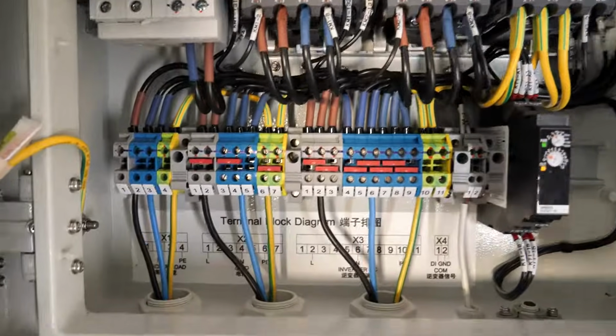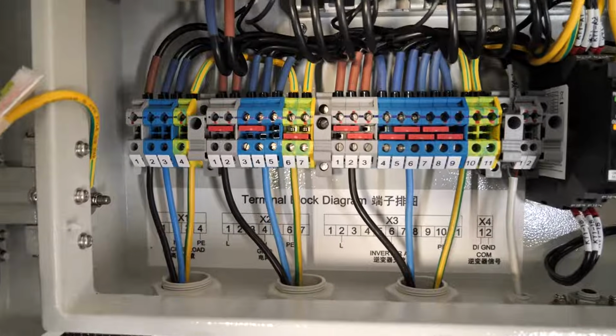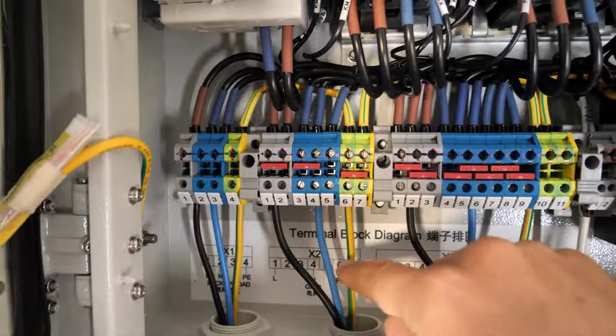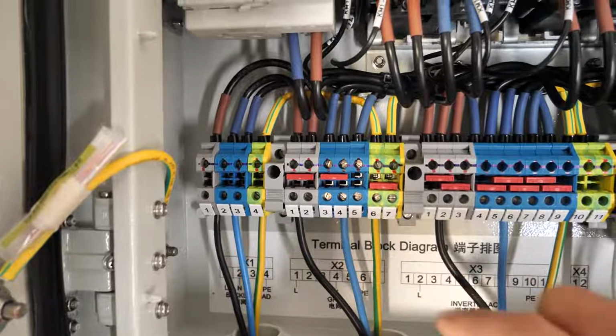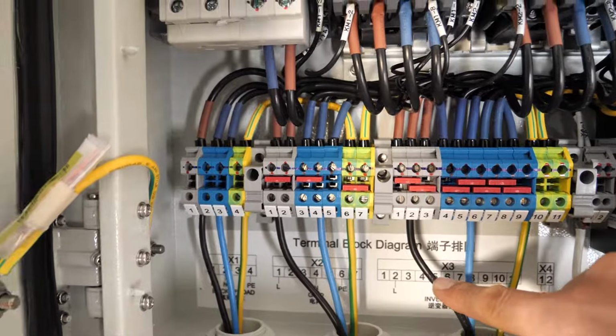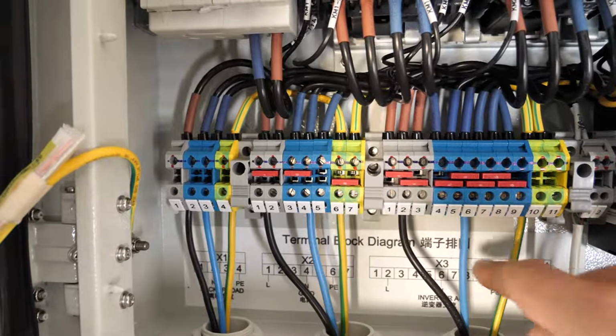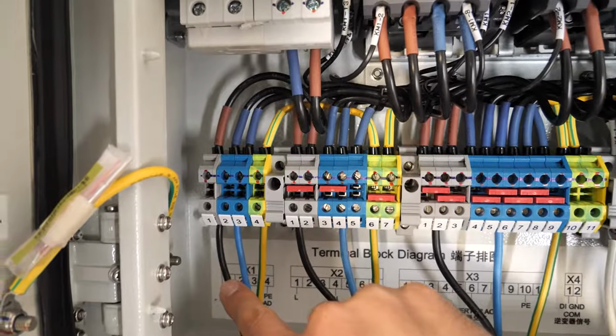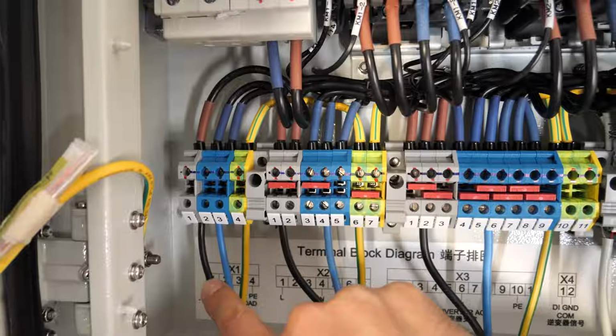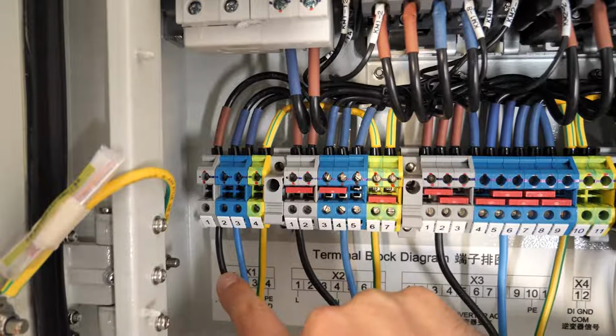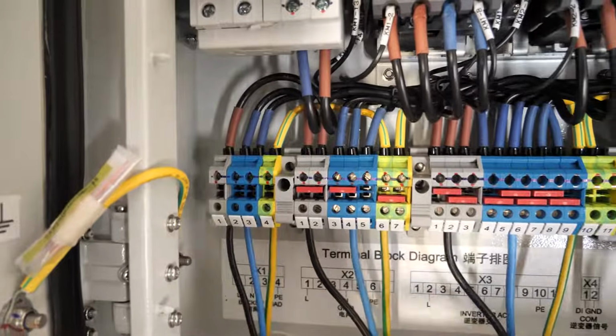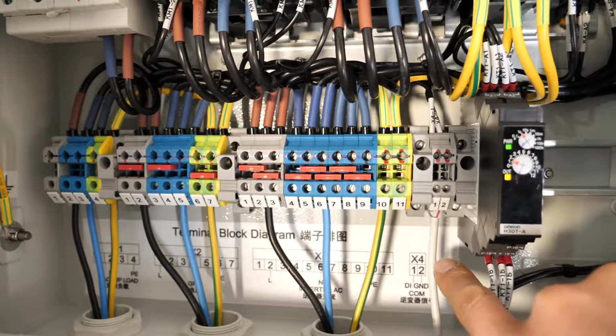Here you can see the wires we are going to connect: phase, neutral and ground that comes from the power company, then the inverter output with phase, neutral and grounding, and the output to critical loads—the output we want to keep working in case of a power failure—phase, neutral, grounding, and then the communication cables with the photovoltaic inverter.